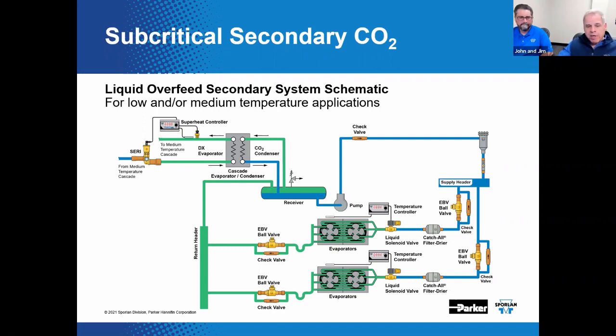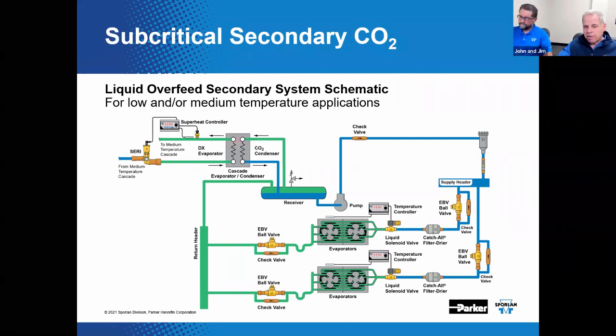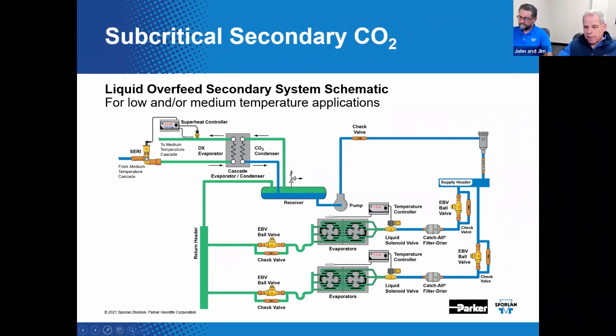That's right. CO2 vapor is siphoned off the top of the receiver, travels to the cascade evaporator condenser up here, and condenses the CO2 vapor to a liquid. The CO2 liquid then returns to the receiver. And the HFC chiller, if you will, ultimately rejects the transferred heat to the ambient or to some other place. That's kind of complicated.